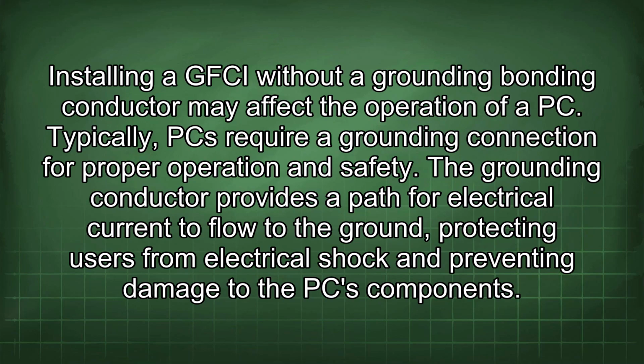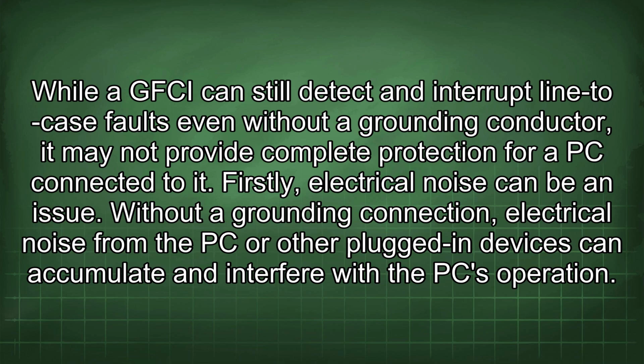Installing a GFCI without a grounding bonding conductor may affect the operation of a PC. Typically, PCs require a grounding connection for proper operation and safety. The grounding conductor provides a path for electrical current to flow to the ground, protecting users from electrical shock and preventing damage to the PC components. While a GFCI can still detect and interrupt line-to-case faults even without a grounding conductor, it may not provide complete protection for a PC connected to it.